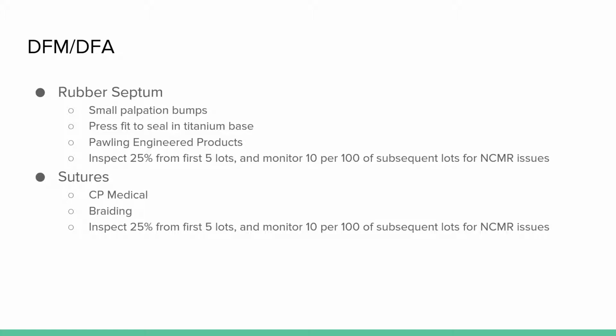For the rubber septum, we would require small palpation bumps in order for the user to identify it in the body, and a press-fit seal in the titanium base. These are fairly specific components that we would have to specify, and we chose Pawling Engineered Products because of their expertise in rubber manufacturing. In order to validate this part, we would inspect 25% from the first 5 lots and monitor 10 per 100 subsequent lots for NCMR issues.